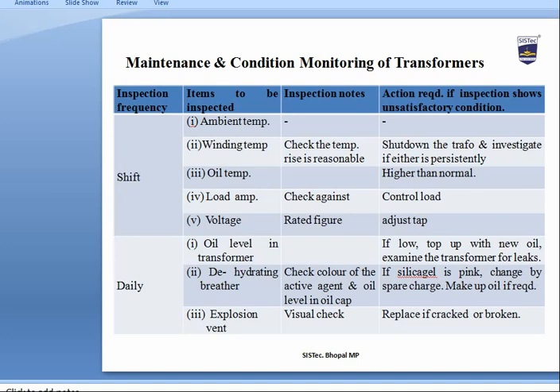Inspection checks include temperature rise, load amperes against rated load, and whether secondary voltage is at the rated value. If winding temperature exceeds design value, the transformer is shut down and investigated. If oil temperature is higher than design value, the transformer is shut down or protection is applied. Daily inspections cover oil level, dehydrating breather, and explosion vent.